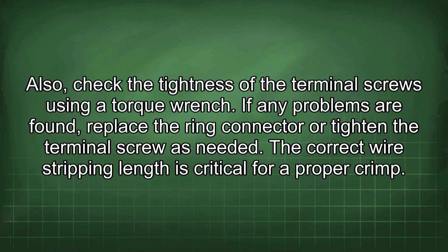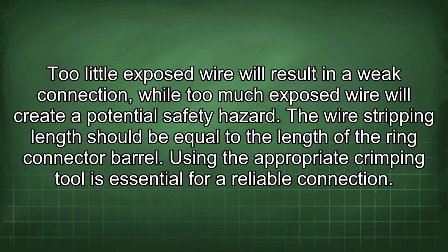The correct wire stripping length is critical for a proper crimp. Too little exposed wire will result in a weak connection, while too much exposed wire will create a potential safety hazard. The wire stripping length should be equal to the length of the ring connector barrel.